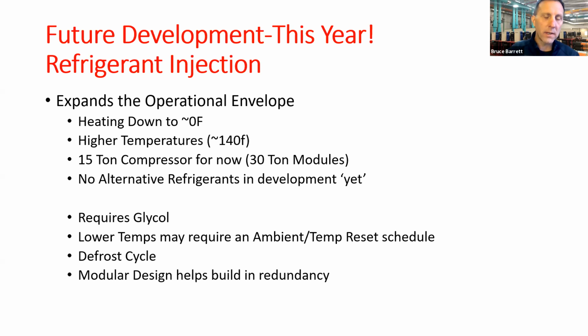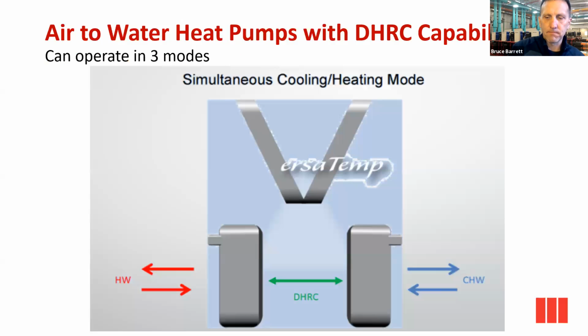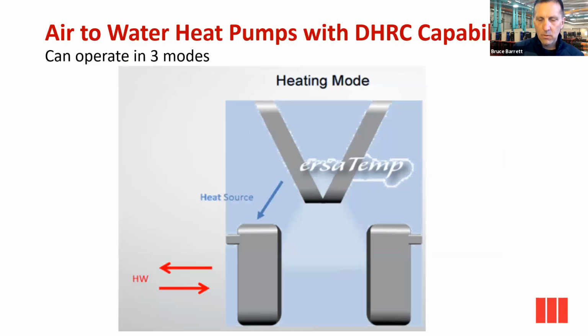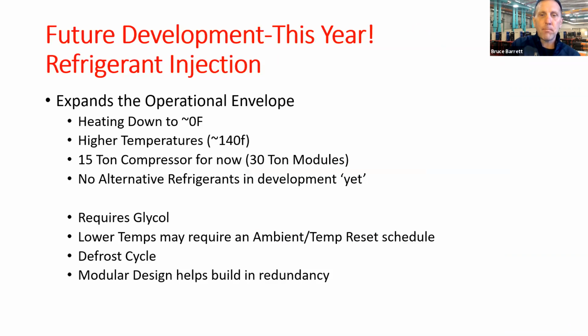To do heating only for any type of this technology, it requires glycol. I'm going to go back 1 slide. When we have a heat source, the air, and we're adding heat of compression, there's dormant refrigerant in the evaporator on the right side of the screen. When you have dormant refrigerant in there and water that isn't moving, you're going to freeze pipes. So we require heating only machines to have glycol on both sides of the machine. Dormant heat exchangers have refrigerant trapped in them. And that's the reason why we require glycol.